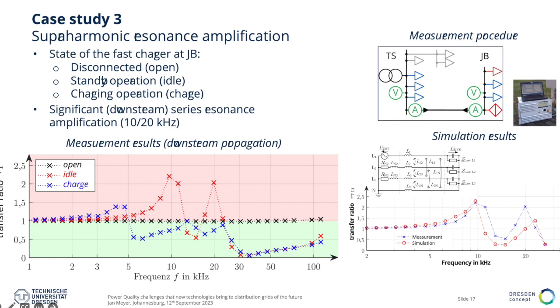Let me show you the measurements. This fast charger, in fact, had 3 operating modes: it could be disconnected, in standby/idle mode, or in charging operation. We put it in all 3 operating states and did this measurement I explained — injecting a signal here at the transformer station and measuring voltages at the transformer station and the junction box.